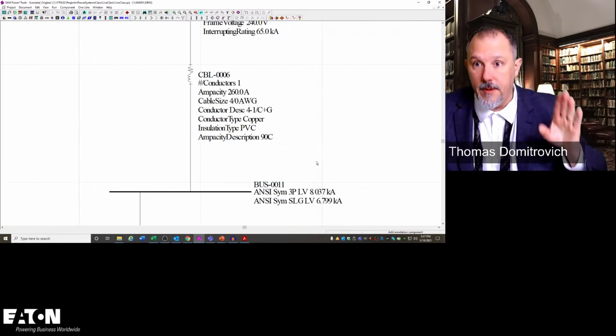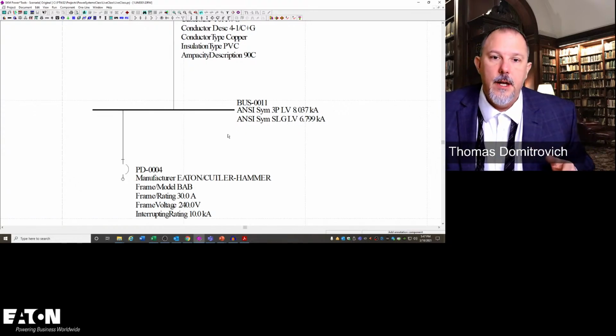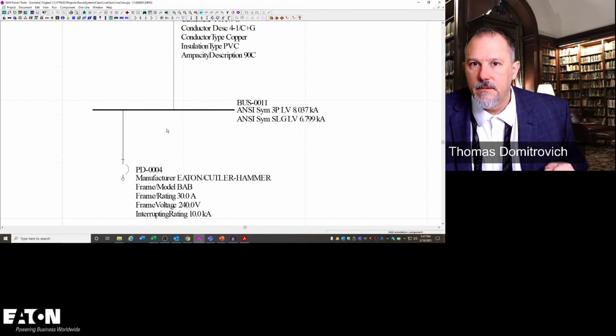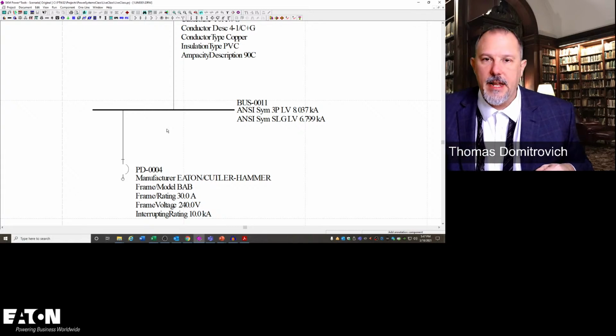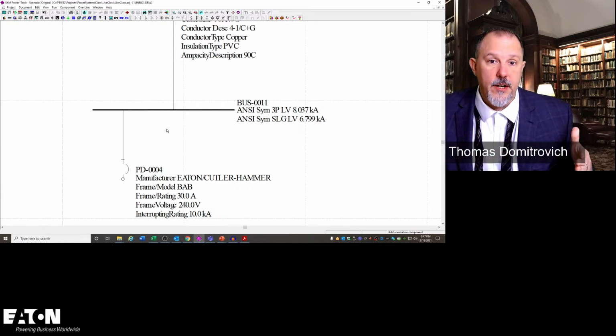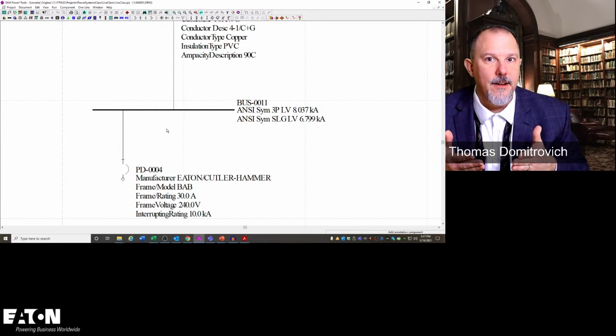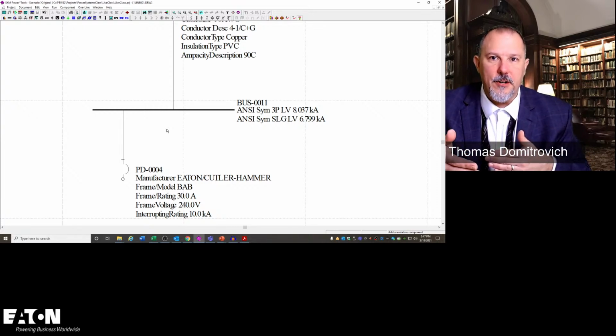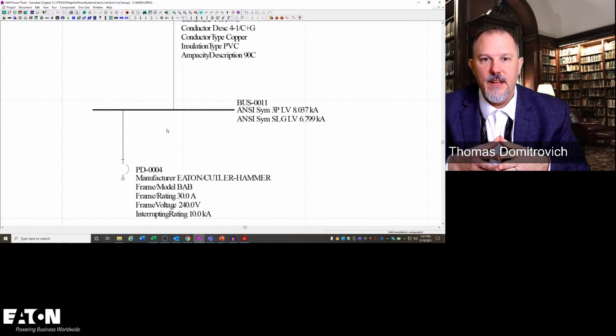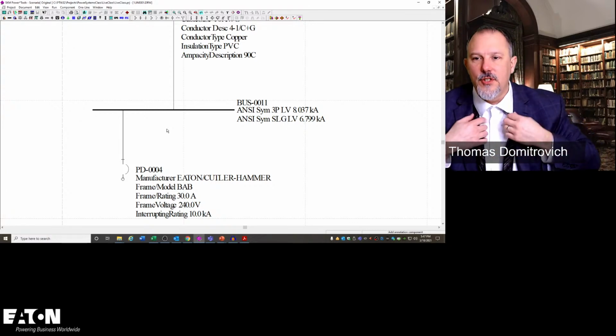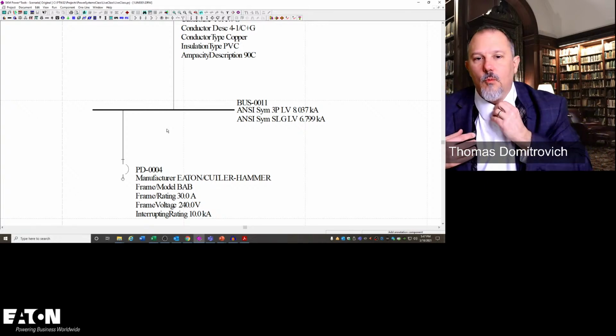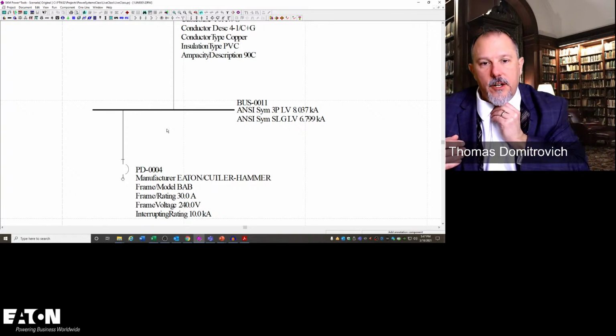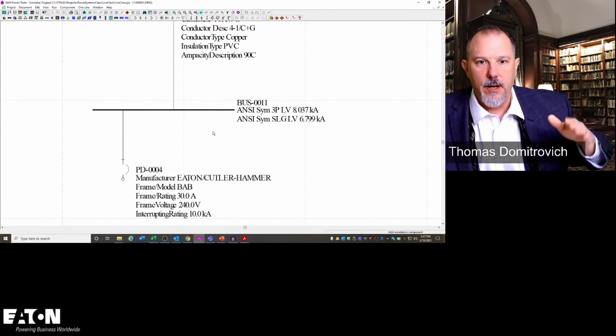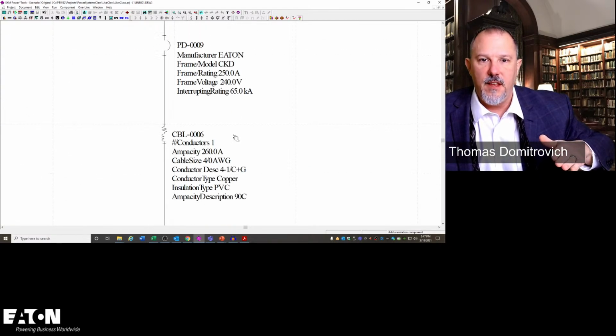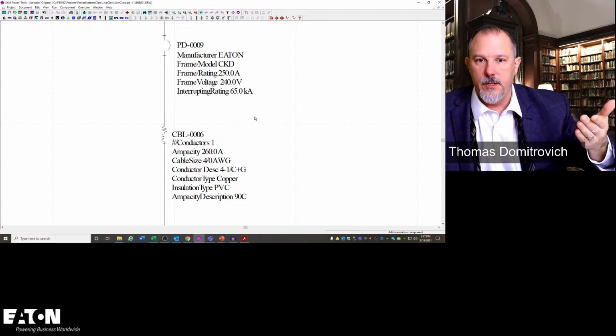Oh, the other thing you have to remember, to MC's point, is there are multiple breakers on this bus. I could have 5 30 amp breakers. Do I have to plot all 5 30 amp breakers? As long as they're the same breaker. If they're all BAB 30 amp breakers, then I only have to plot one. So typically, a lot of people will do these in training classes, we'll just pick the largest breaker. We'll pick the largest breaker downstream and plot it against the feeder breaker upstream. That's just what we do.